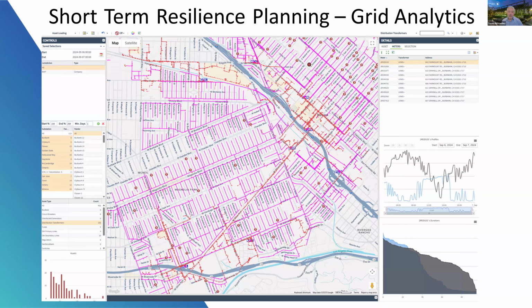So as I'd mentioned before, we do use grid analytics to analyze the overloaded transformers and, in general, assets that are being overloaded in our system. The grid analytics pulls data in from all of our 54,000 plus AMI meters. What we get here is an idea of which transformers are overloaded in our system, where they're located, how much they're overloaded, and for how long. That gives us a really good idea of which transformers we need to target and helps us prioritize which transformers are being replaced, because obviously we can't go out and replace all of them. We've got about, I think, 6,000 plus distribution transformers.